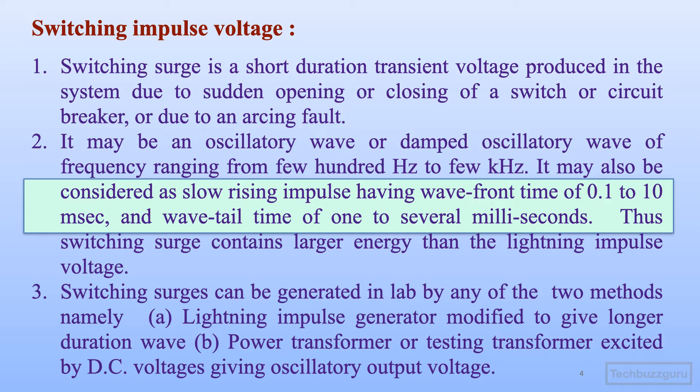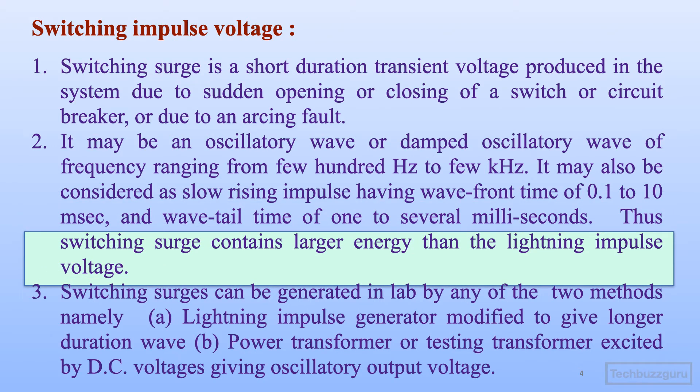Thus the switching surge contains a larger amount of energy when compared with the lightning impulse voltage. If you recollect, the lightning impulse voltages have rise time of 1.2 microseconds and fall time of 50 microseconds. With the same peak amplitude, switching surges have rise time and wavetail time in the range of several milliseconds. That's why the energy content of switching surge is higher than the lightning impulse.